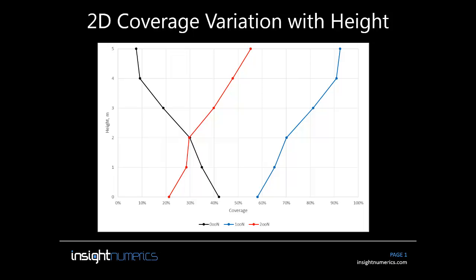So now we reach a critical issue. How do we choose which height to use? Typically you can't say which height a fire will start, and fires themselves are 3D and by nature cut through several heights, so it's a completely subjective decision. If you follow this line of reasoning to the end, it means that with 2D mapping, whether you comply with performance criteria or not is completely based on a subjective decision of which height to use.